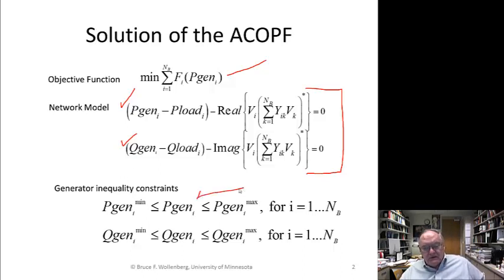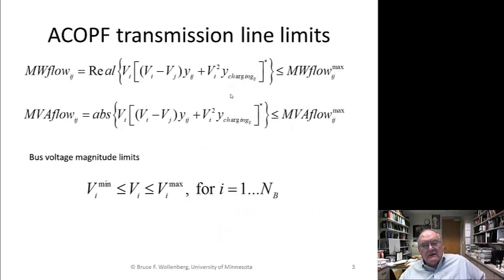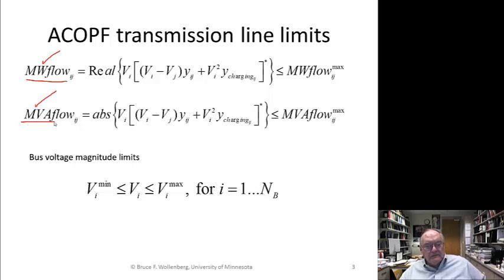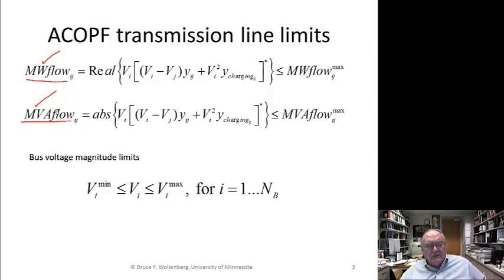We add the generation inequality constraints on P and Q into the problem. Now we're dealing with reactive power, so I can put the Q constraints right into the problem as well. I can put transmission constraints and restrict either megawatt flow or MVA flow. Sometimes it's useful to put MVA flow, or current flow limits if desired. Usually we do either megawatt or MVA flow limits on transmission lines or transformers. Transformers are often rated in MVA.